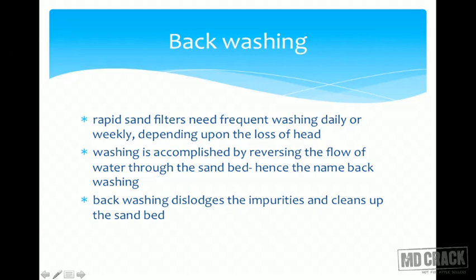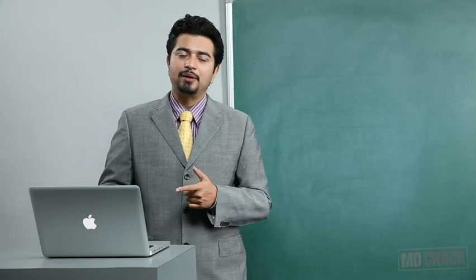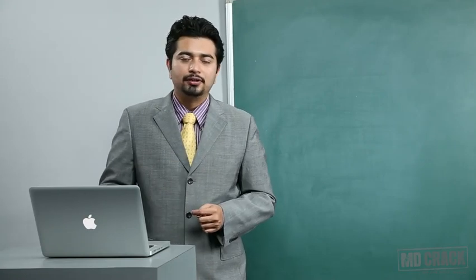Washing is accomplished by reversing the flow of water through the sand bed — hence the name backwashing. The water flows back, dislodges all the impurities towards the top, and the filter is cleared. Water that was flowing downwards now flows upwards, and thus the filter gets cleared. Remember, slow sand filter cleaning was done by scraping, whereas the rapid sand filter is cleaned by backwashing.